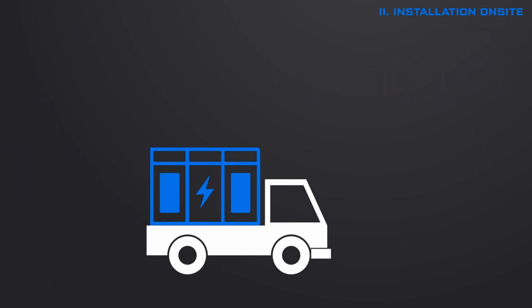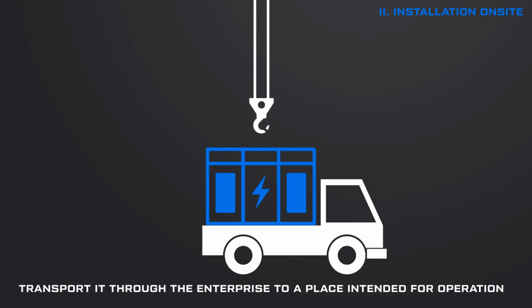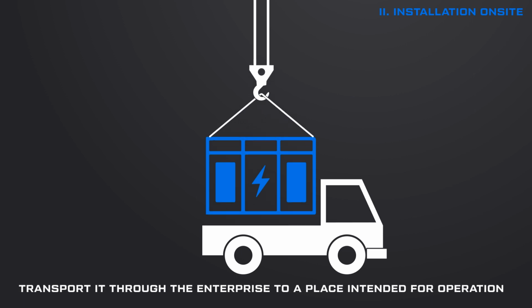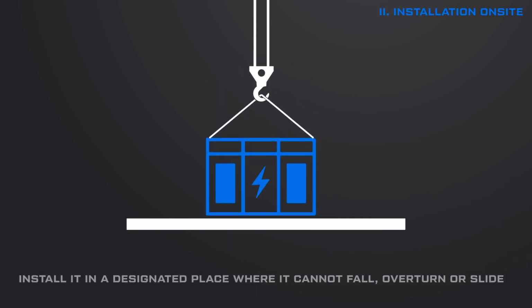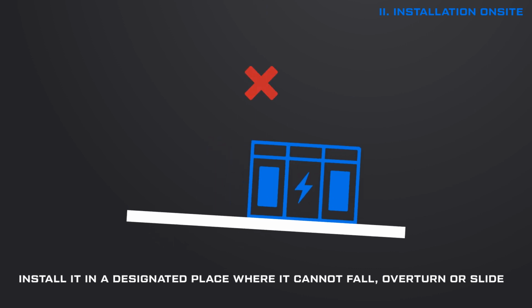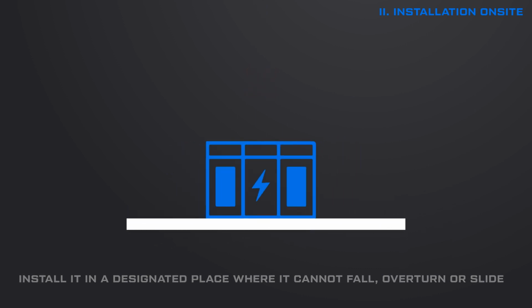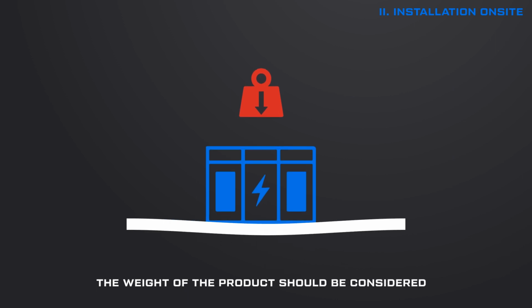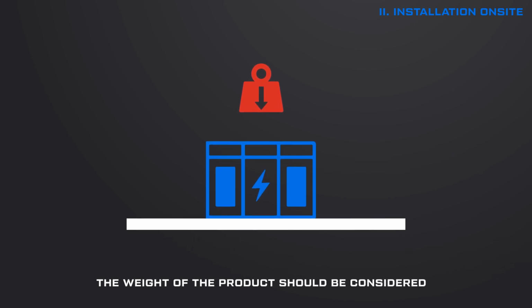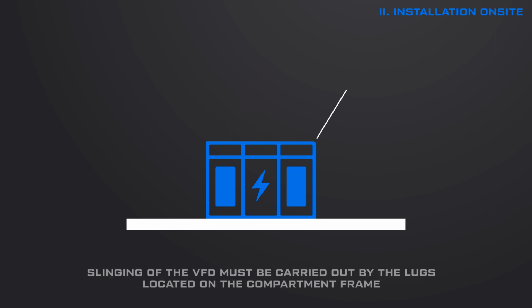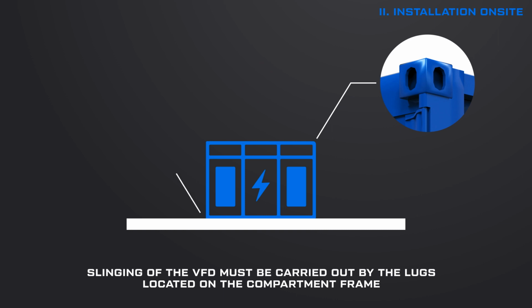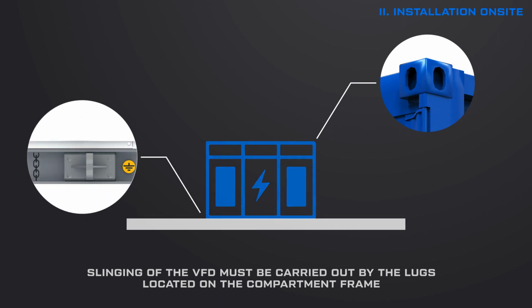To install the AT27, it is necessary to transport it through the enterprise to a place intended for operation and install it in a designated place where it cannot fall, overturn, or slide. When choosing a location for the installation of the equipment, the weight of the product should be considered to avoid destruction of floors and foundations. AT27 equipment weight is indicated on the nameplate, which is located on the front of the equipment. Slinging of the VFD must be carried out by the lugs located on the compartment frame.